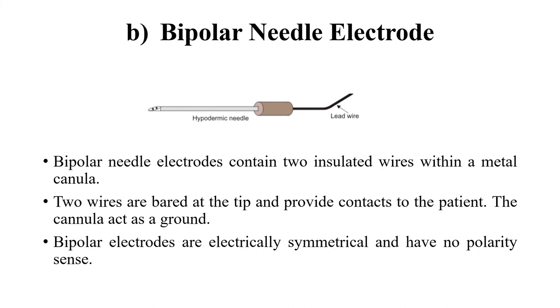Now we will discuss the bipolar needle electrode. The figure shows this electrode — from the name, we can say that two wires are placed within the lumen of the needle and connected differentially. Bipolar needle electrodes contain two insulated wires within a metal cannula. A cannula is a tube that can be inserted into the body of the patient — for example, during delivery or to take fluid samples. The two wires are bared at the tip and provide contact to the patient, while the cannula acts as a ground. Bipolar electrodes are electrically symmetrical and have no polarity sense.